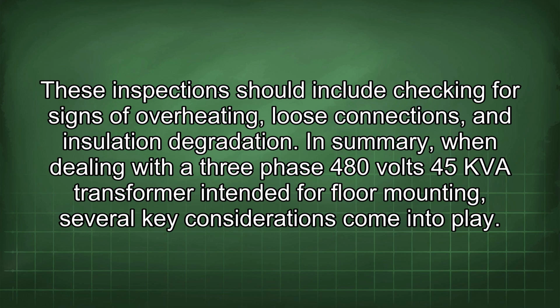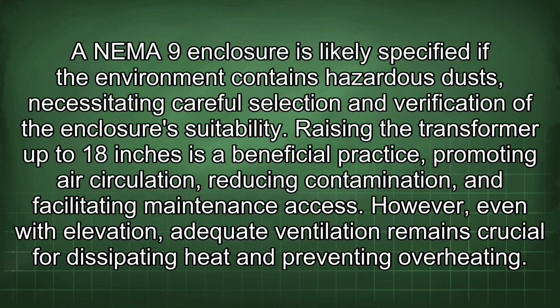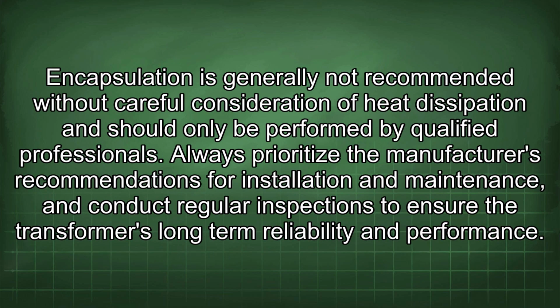In summary, when dealing with a 3-phase 480 volts 45 kVA transformer intended for floor mounting, several key considerations come into play. A NEMA 9 enclosure is likely specified if the environment contains hazardous dusts, necessitating careful selection and verification of the enclosure's suitability. Raising the transformer up to 18 inches is a beneficial practice, promoting air circulation, reducing contamination, and facilitating maintenance access. However, even with elevation, adequate ventilation remains crucial for dissipating heat and preventing overheating. Encapsulation is generally not recommended without careful consideration of heat dissipation and should only be performed by qualified professionals.